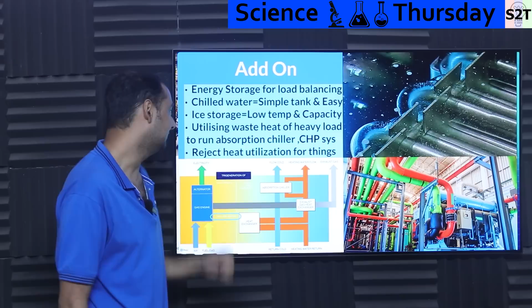Liquid at 0 degrees Celsius is a very good conductor, so the benefit is you get almost 1 degree Celsius coolant temperature. Really good capacity, this is where this shines. The capacity is monstrous, meaning if you give 100 kiloliters of tank capacity, the energy stored in ice versus liquid water isn't even a competition. Chilled water might give you 1 hour of chilling time.